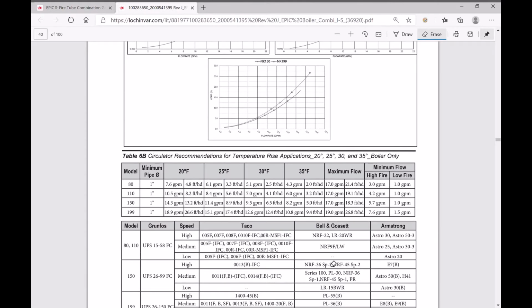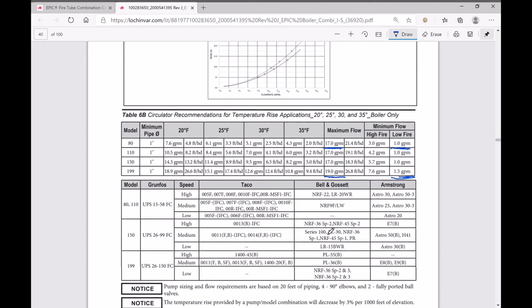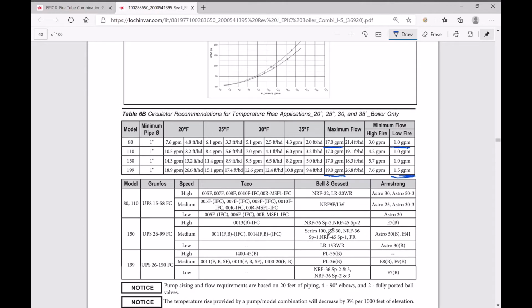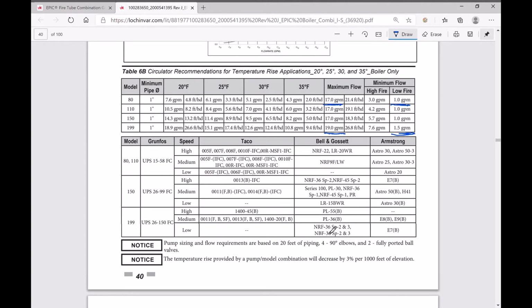Now let's go down here and look at our flow rates. So the maximum flow rate of the Epic boiler on the 199 is 19 gallons per minute. The minimum is 1.5 gallons per minute. That's a pretty large range of flow rates to work with. On the smallest boiler, we have 17 gallons per minute, and on low fire, our lowest range is 1 gallon per minute. And again, because that heat exchanger has such low resistance, we can sort of have variable flow through that heat exchanger. And down here, we can see the recommended pumps.